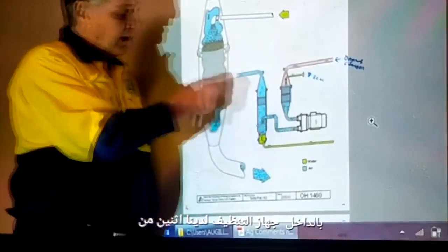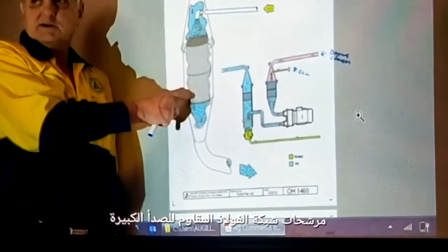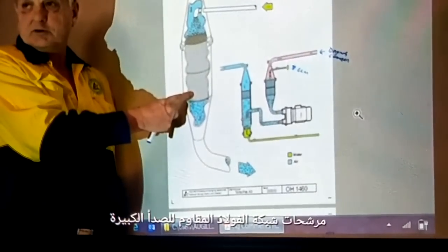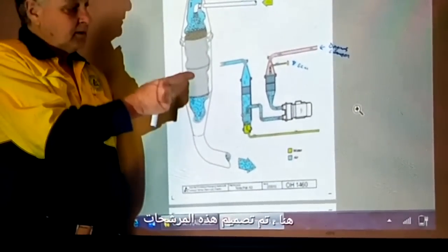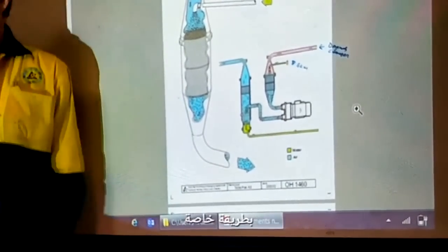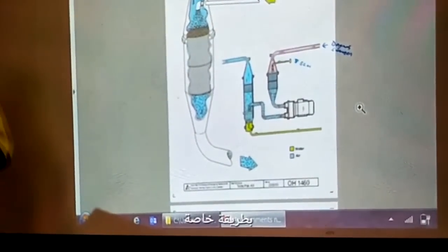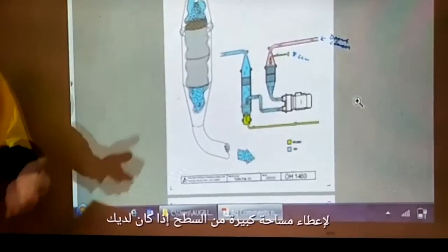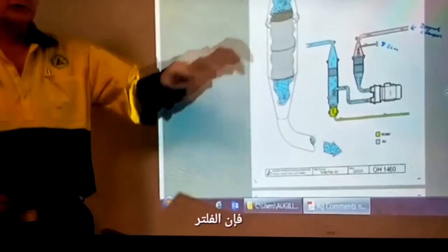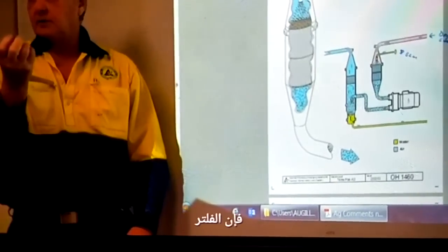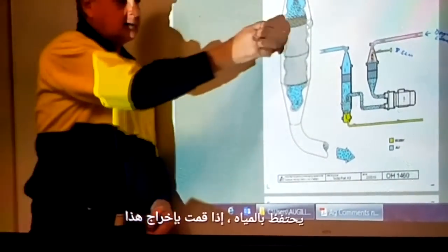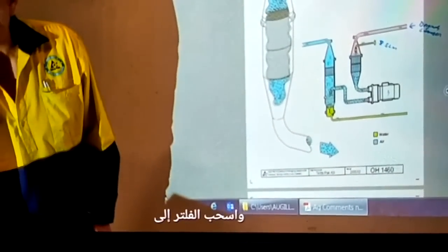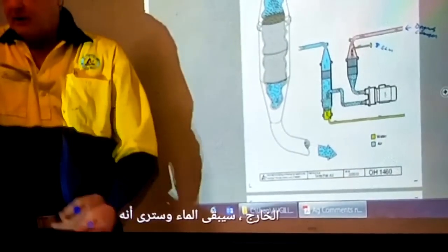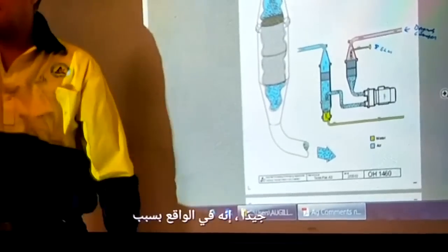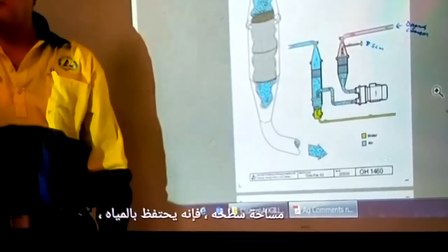Inside the scrubber, we have 2 big stainless steel mesh filters here. These filters are designed in a special way to give a lot of surface area. The filter holds water. If you take this filter out, put it in a bucket of water, pull the filter out, the water will stay, and you'll see it drain out. Because of its surface area, it holds water.